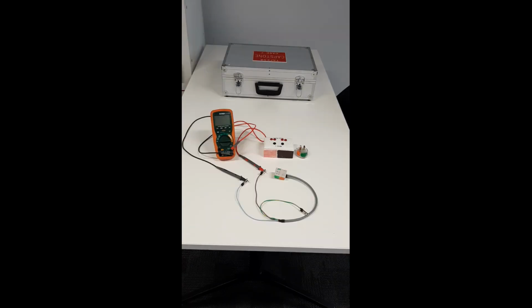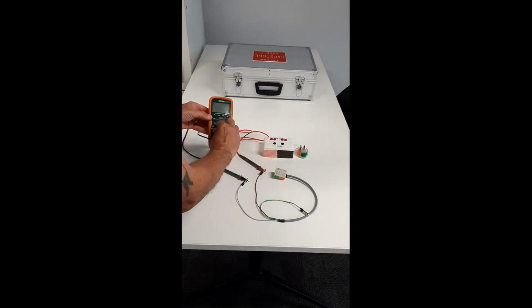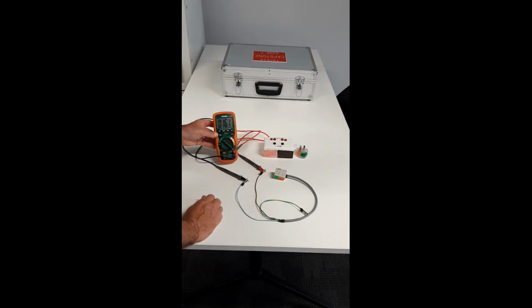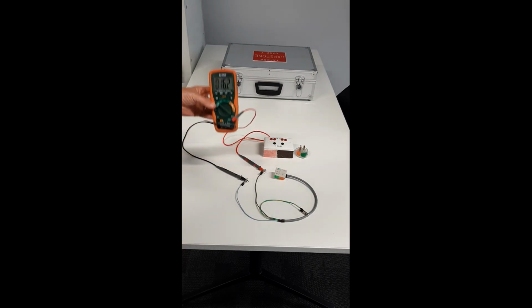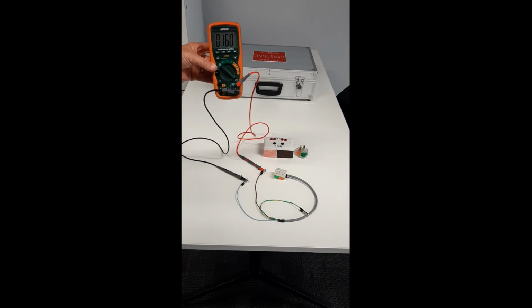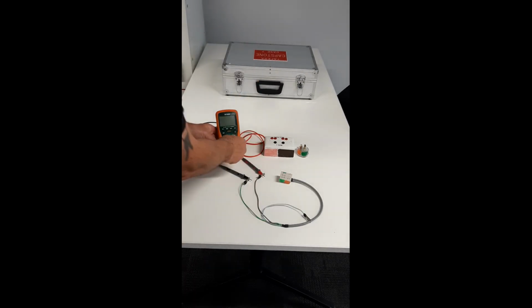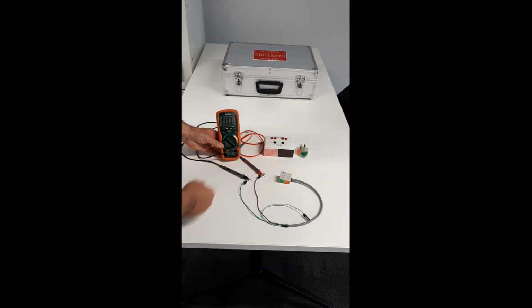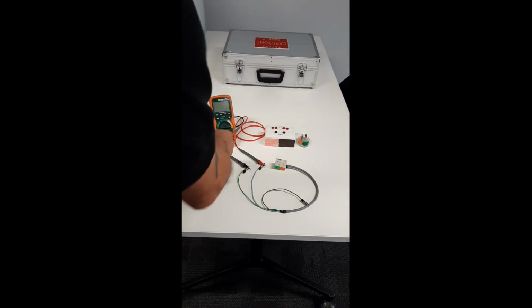Check the polarity resistance tester. To check that the resistances are active to neutral, 15 ohms. I'm getting approximately 16.2 ohms with this multimeter. Active to earth. My result is 11 ohms. Neutral to earth.